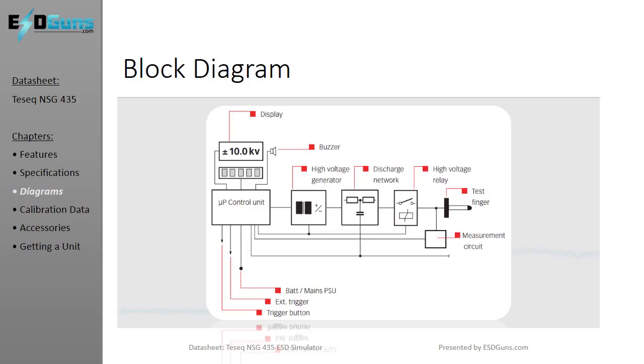Microprocessor controls and monitors all the generator functions. The battery charge state is also continuously monitored. The instrument's functions are inhibited once the battery voltage is insufficient to guarantee the pulse parameter. The high voltage generation is dynamically controlled by the processor. Varying load conditions, supply voltages, etc. can thus be taken into account and have no effect on the pulse parameters. The charge voltage to the network is kept constant as long as the trigger is active. The high voltage is discharged internally when the trigger is reset.